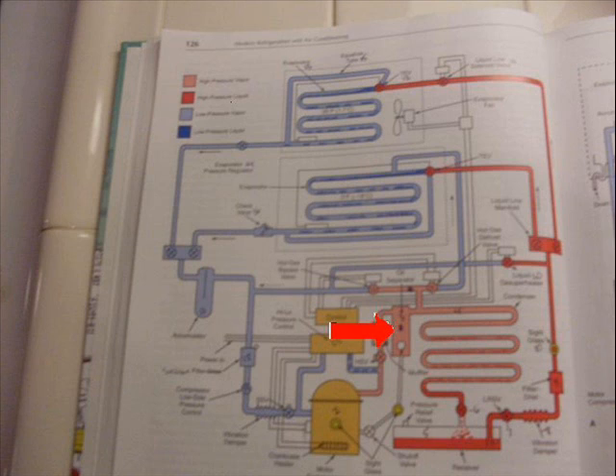The other style of oil separator is called an impingement style. It uses a series of metal screens on the inlet and outlet. The concept is that the hot high pressure gas with oil in it strikes the screens. The oil condenses onto the screens and falls off to the bottom of the tank in the little oil receiving area. And then the oil is returned back to the compressor via the same type of oil float valve.